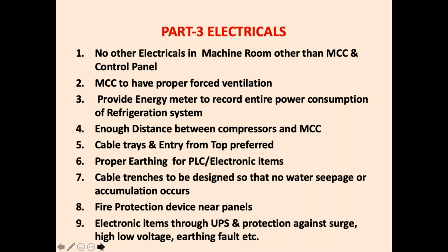Every day you should be able to record that today's production was so much and I have consumed so much energy. Then only it will give you guidelines on where the mistakes are taking place, and why your power consumption is going up. Enough distance between the compressors and the motor control center, MCC, should be available. MCC should not be very, very close to the compressor because compressors get overheated.